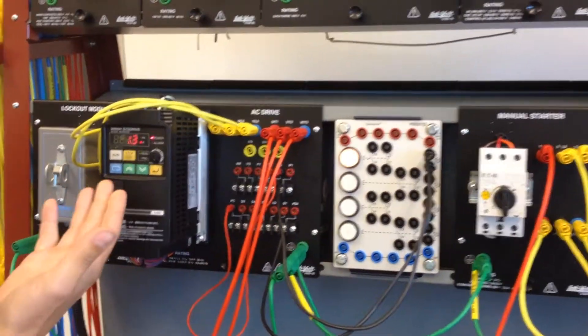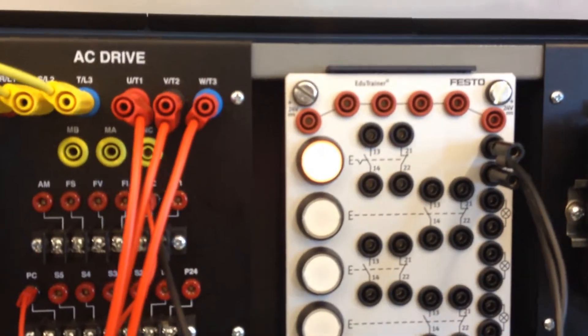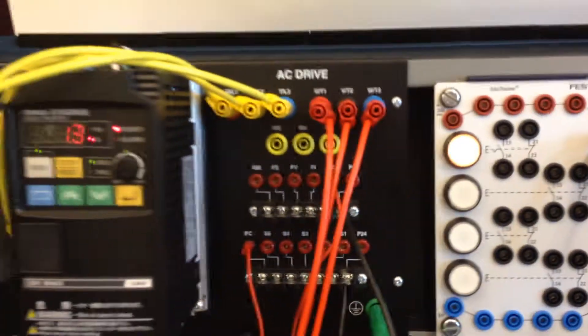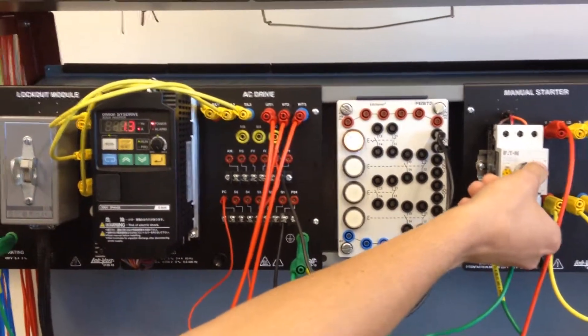As you can see our VFD is reading 1.3 amps, and our light is on to say that overcurrent has been reached. I can turn the load off and our light should go off and our motor will go back to drawing 0.9 amps.